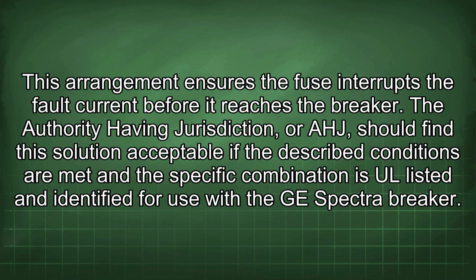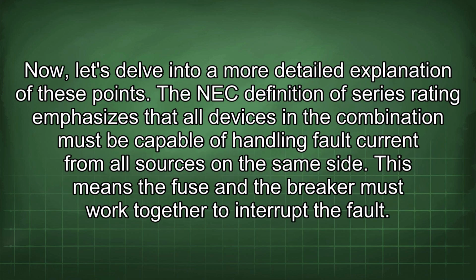This arrangement ensures the fuse interrupts the fault current before it reaches the breaker. The authority having jurisdiction, or AHJ, should find the solution acceptable if the described conditions are met and the specific combination is UL listed and identified for use with the GE Spectra breaker. Now let's delve into a more detailed explanation of these points. The NEC definition of series rating emphasizes that all devices in the combination must be capable of handling fault current from all sources on the same side. This means the fuse and the breaker must work together to interrupt the fault.